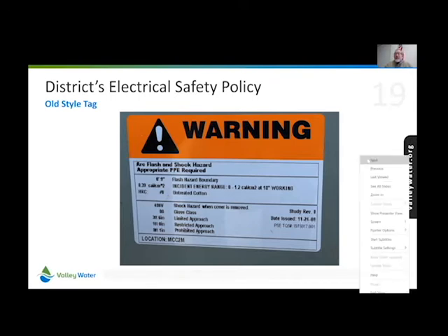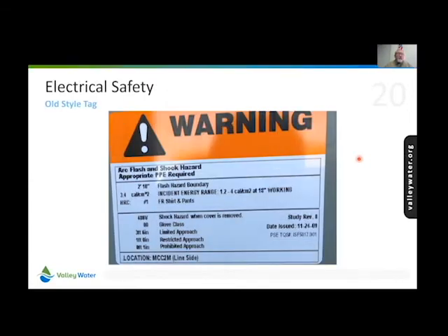Let me show you the next one here. This one shows 3.4. So what's the difference between those two? Well, any incident energy above 1.2, as you can see right here, 1.2 to 4 calories, that is where the arc flash shirt and pants requirements come in. If you're dealing with 1.2 calories and below, it's good to wear that stuff, but at that point, you're dealing with shock hazard only.